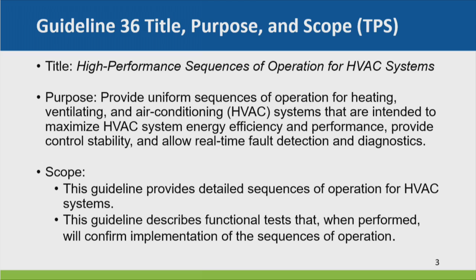We have another research project that I'm on, which we're doing through the state of California, to come up with some testing that would be used by the manufacturer. Everybody's familiar with BACnet, I'm sure. BACnet has BTL, the BACnet Testing Laboratory, and they have these testing mechanisms that allow you to test your product to see that it meets the BACnet standards. Our intent is to do the same thing here, so that you'd be able to test your implementation of the Guideline 36 sequences and get a pass-fail out of it. So we have a project working on that.